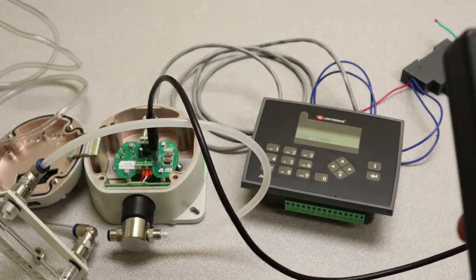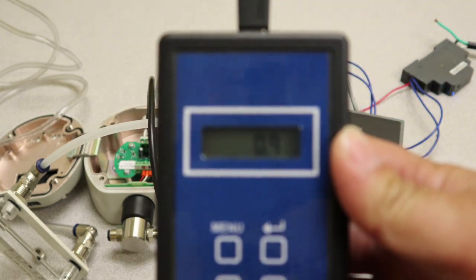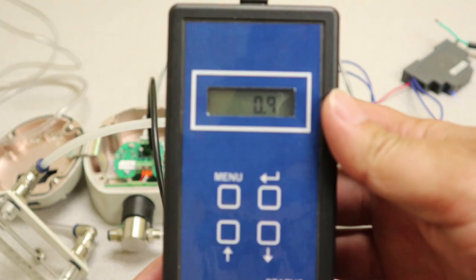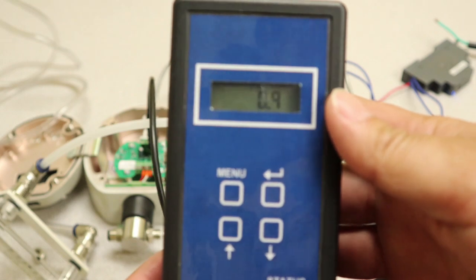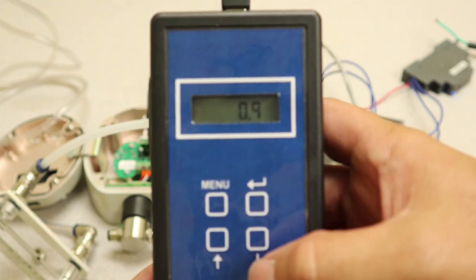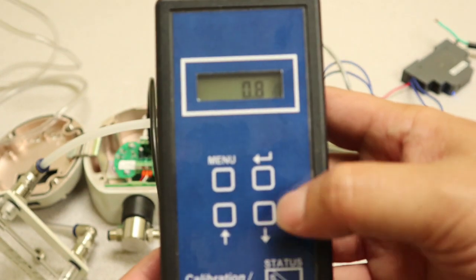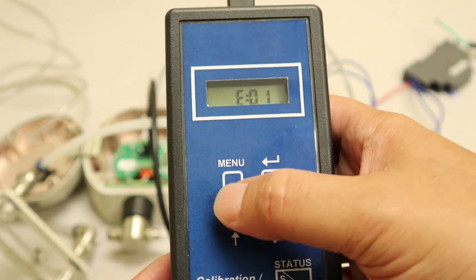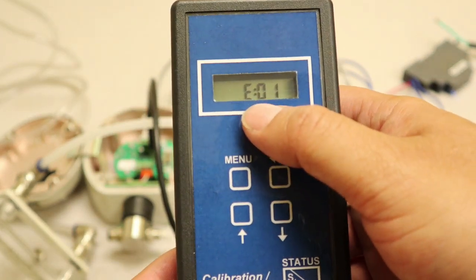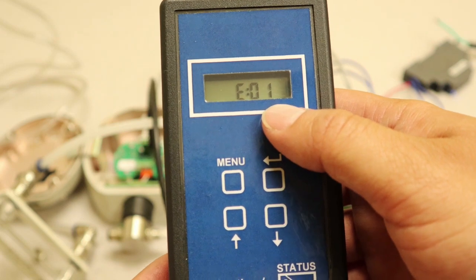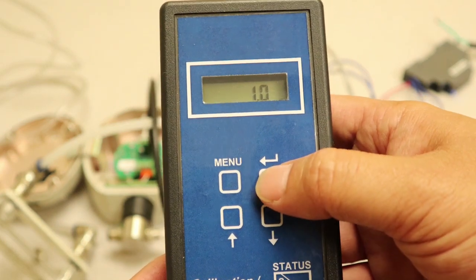After connecting it for about a minute, or when the reading starts stabilizing like this, it's bouncing around 0.9, which is still fine. We're going to press the arrow up menu, and we're going to do E01. So once you see E01, hit enter.